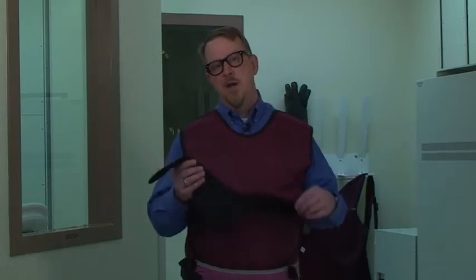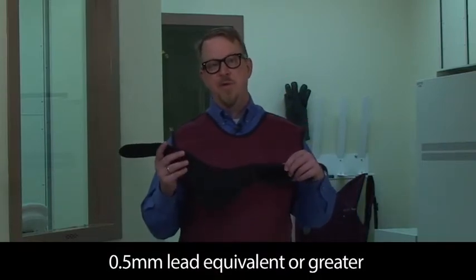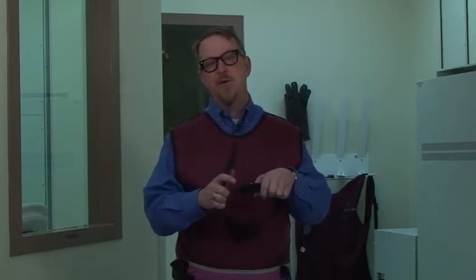This gland is sensitive to radiation and should be shielded whenever possible with a thyroid shield of 0.5 millimeter lead equivalent or greater. A thyroid shield is fairly lightweight, wraps around the neck, and is secured to the back with Velcro. Although the radiologic technologist should avoid intersecting the primary beam if possible, sometimes it's unavoidable, especially during fluoroscopy.